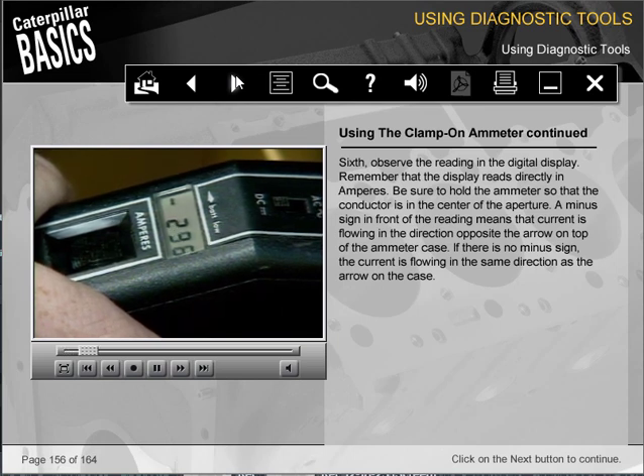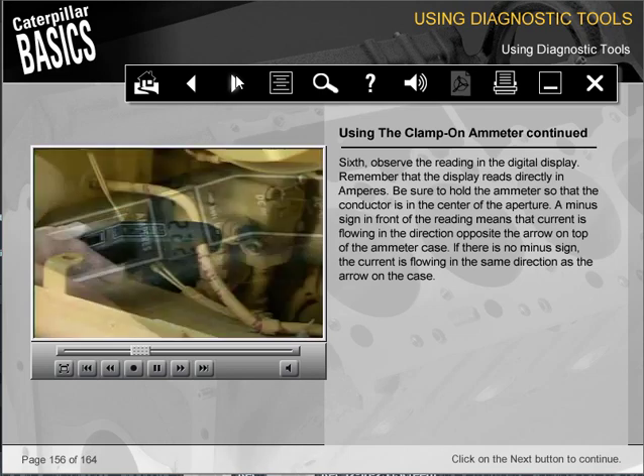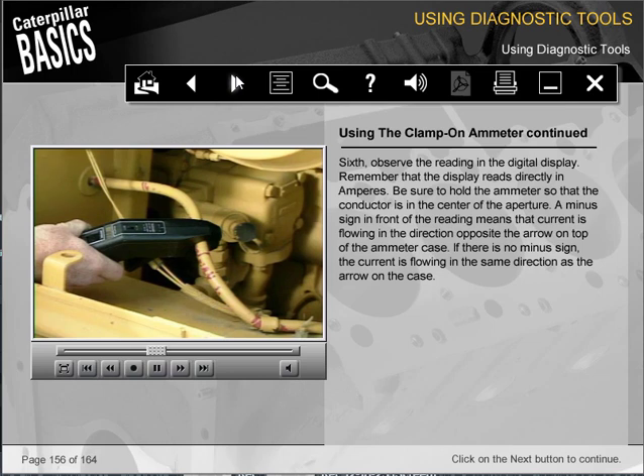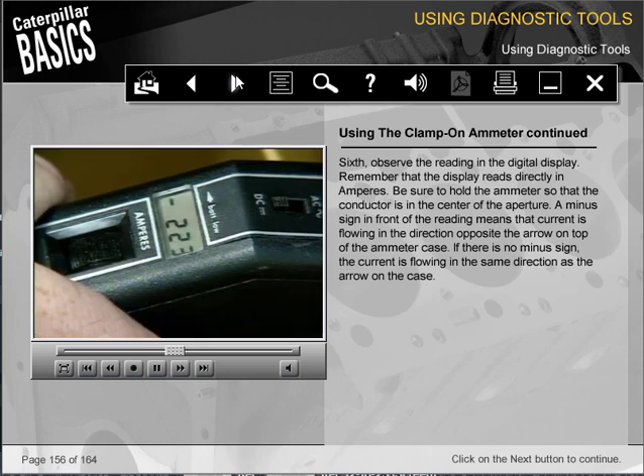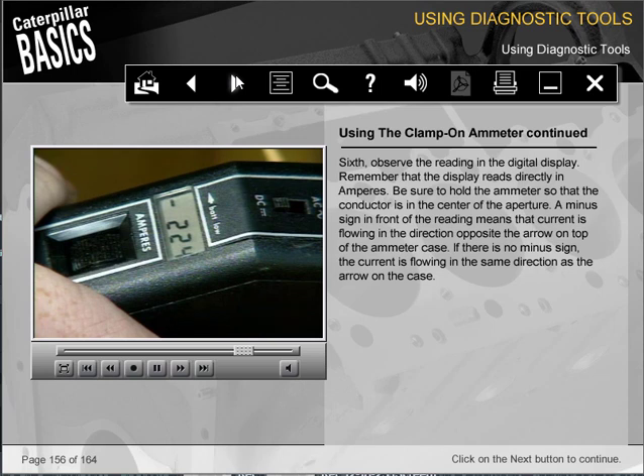Sixth, observe the reading in the digital display. Remember that the display reads directly in amperes. Be sure to hold the ammeter so that the conductor is in the center of the aperture. A minus sign in front of the reading means that current is flowing in the direction opposite the arrow on top of the ammeter case. If there is no minus sign, the current is flowing in the same direction as the arrow on the case.